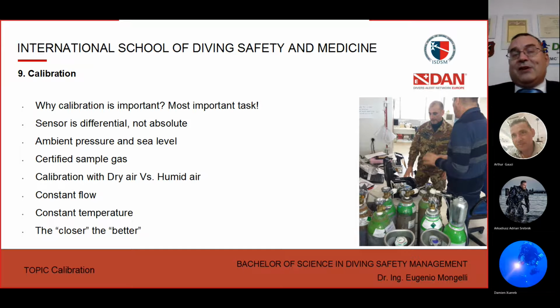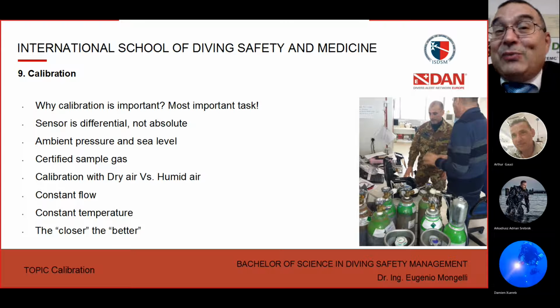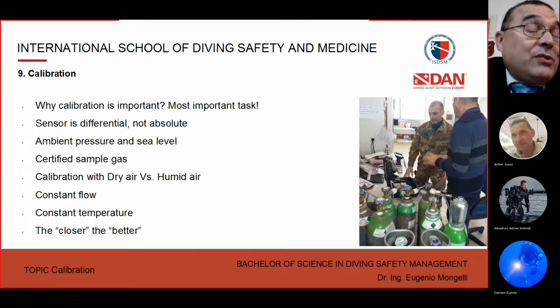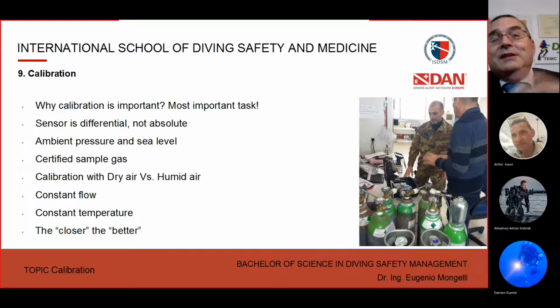Luckily, in diving, we are very lucky because we have air available, and we always have a cylinder filled with air in a diving center. And we generally have pure oxygen. So that is the main gas that we may use for calibrating the analyzers. In this way, you may do the calibration.